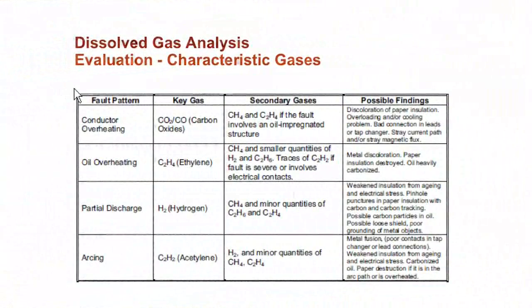But the one thing I want to stress is, you can do all this, but end of life cellulose doesn't necessarily mean that it has a high risk of failure. However, as I was saying before, if you have a cellulose that has reached the end of its life, it's more susceptible to a dielectric risk of failure. So it's not necessarily that the thermal part of it fails it. It's more susceptible to other things.